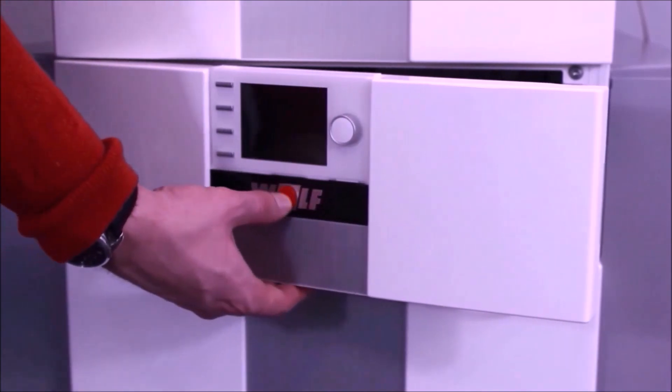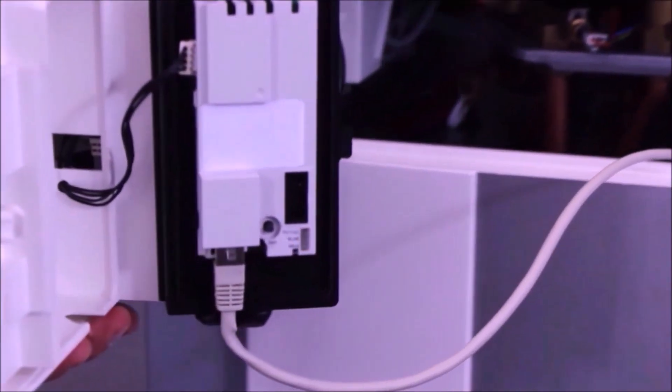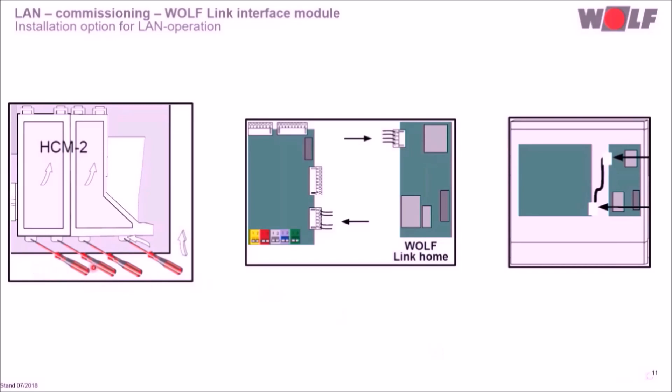The connection cable is integrated in the control system casing for the gas condensing unit CGB-2 in all variants and for the split heat pump. We connect the module and the router with the LAN cable and press the power button again. The module is supplied with voltage, the yellow eBus LED starts to flash, and once it lights constantly the connection was successful. The flap can be closed and the control system casing swung back. You can also mount the WolfLink Home in the electrical connection box next to the HCM2 board using the included connection cable.